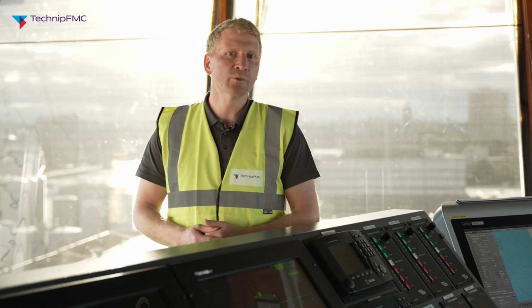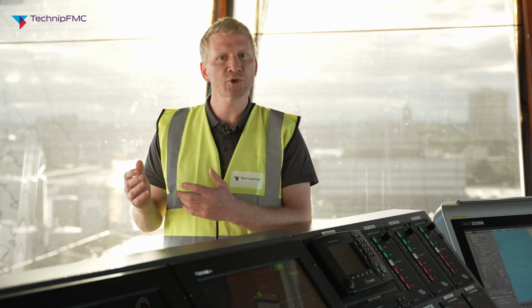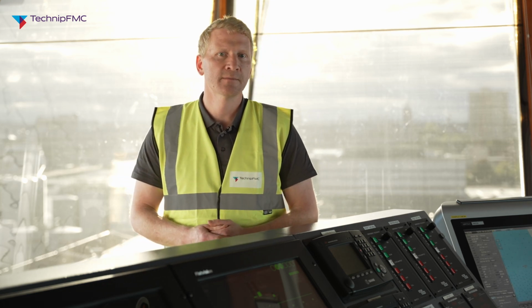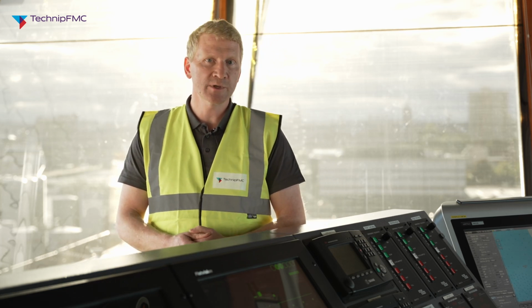So now let's talk about the emission reduction benefits. Fundamentally, we want to run fewer engines at higher load where they run more efficiently. When the vessel's in port, we can reduce from 2 engines down to 1, or potentially to 0 where we have shore power infrastructure available. When the vessel's in transit, we don't reduce the number of engines, but we benefit from the peak shaving we discussed. And when the vessel's offshore working in DP, we reduce from 4 engines down to 2. If we take those modes across an average year for Deep Arctic, we expect to see savings of up to 20% in fuel and emissions, as well as around 50% reduction in engine maintenance and running hours.